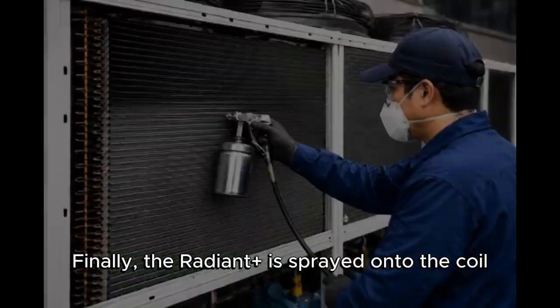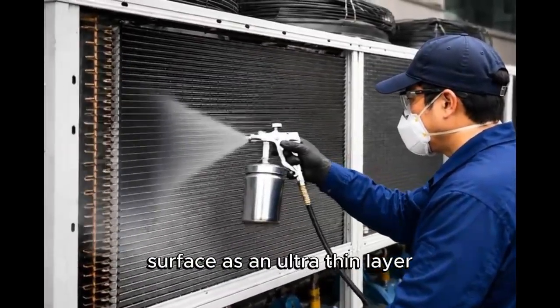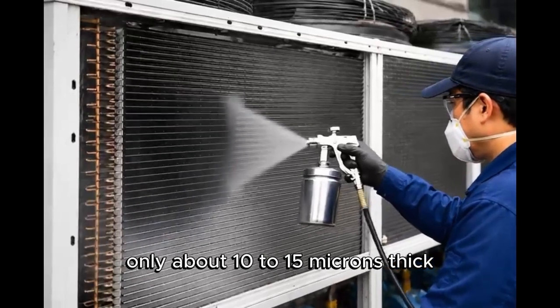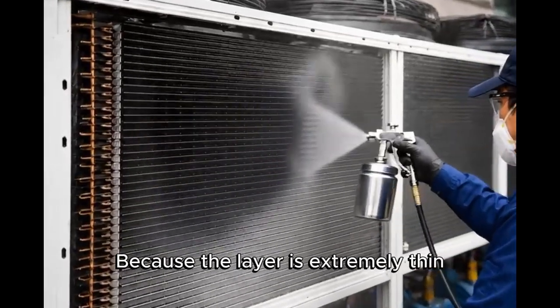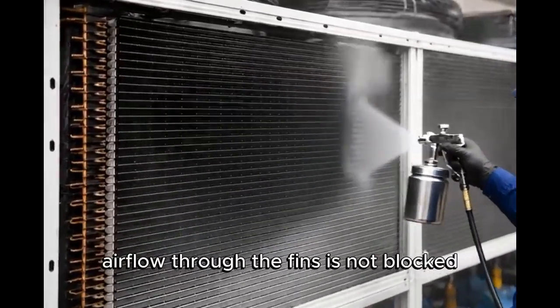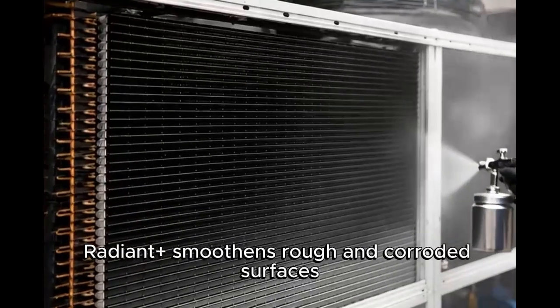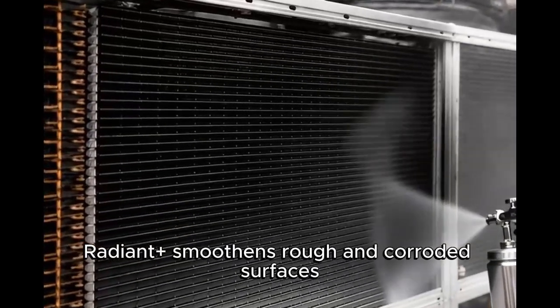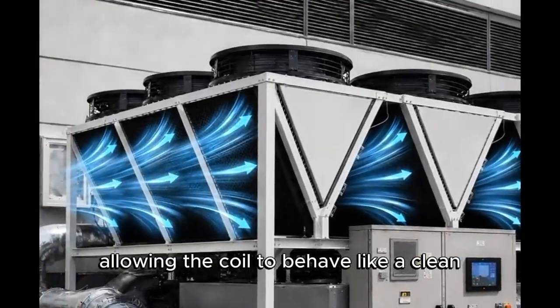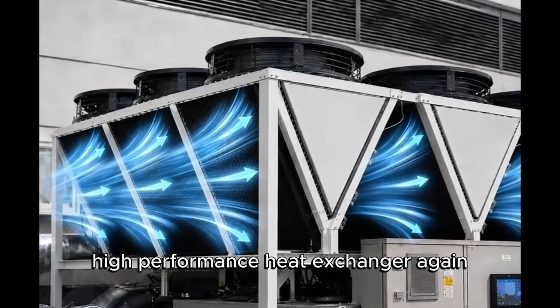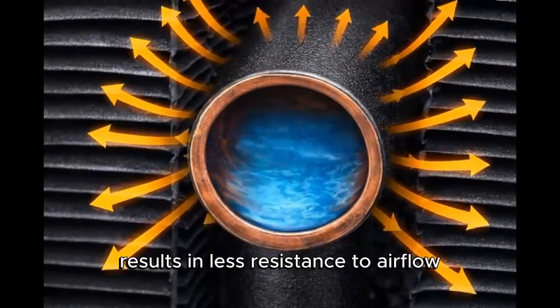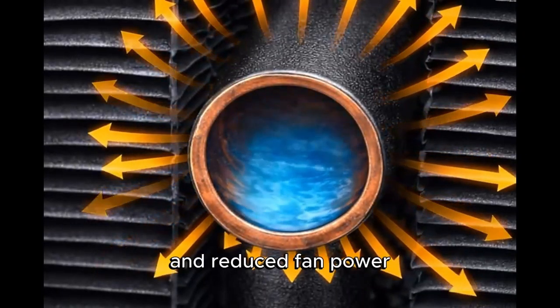Finally, the Radiant Plus is sprayed onto the coil surface as an ultra-thin layer, only about 10 to 15 microns thick. Because the layer is extremely thin, airflow through the fins is not blocked. Instead, Radiant Plus smoothens rough and corroded surfaces, allowing the coil to behave like a clean, high-performance heat exchanger again. This in turn results in less resistance to airflow and reduced fan power.